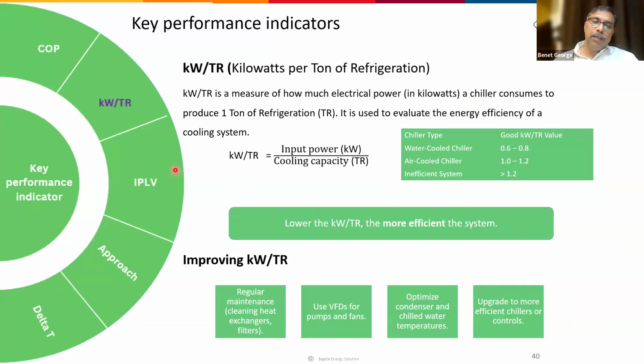Similar to COP, we can have kilowatt per TR. How much kilowatt per 1 ton of refrigeration? So the lower the kilowatt per TR, the more efficient it is. Typically for a water cooled chiller you can get 0.6 to 0.8, but the latest chillers, like magnetic chillers, even come at 0.4. Air cooled chillers come at 1 to 1.2.